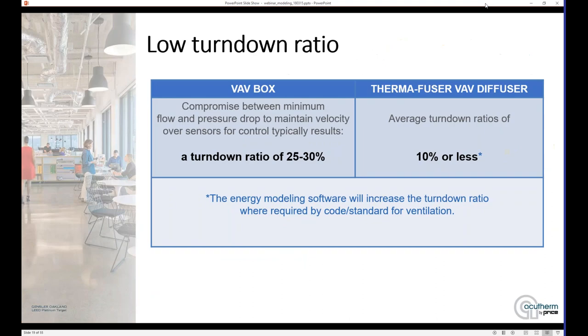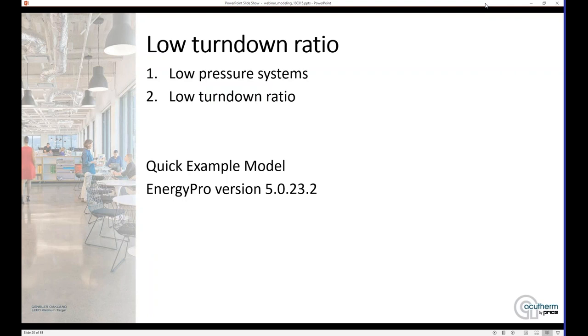Second, we're going to take a look at the low turndown ratio. When you're designing your VAV box system, you've got this compromise between velocity and turndown, and it usually results in a turndown ratio of around 25% to 30% for the box. The Thermafuser diffusers can average 10% or less on their turndown — a much lower turndown. This is useful when you're trying to reduce reheat or the need for heat in your building. The software also takes into account ventilation codes and standards, so if there are spaces where you're not allowed to turn down that far because you've got to maintain your minimum ventilation, the energy modeling works that in and prevents that from happening.